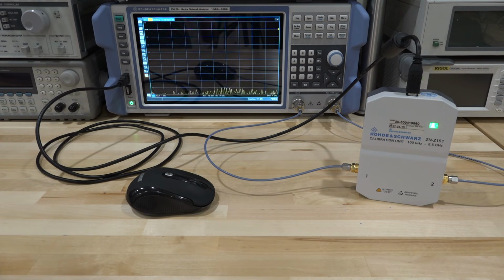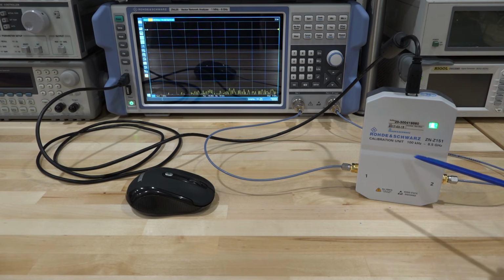A good place to start using the instrument is, of course, to calibrate it. Now, you can calibrate the network analyzer using a calibration kit if you have one, or you can use a Rohde Schwarz calibration unit. This is an automatic calibration unit. This particular one is the ZNZ151, and it goes from 100 kHz to 8.5 GHz. This is a 2-port SMA calibration kit with a USB connection directly to the instrument.